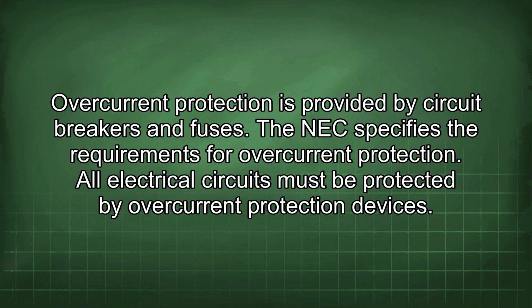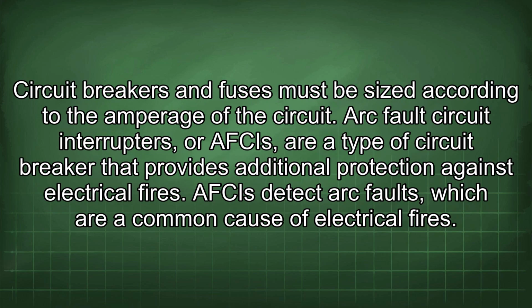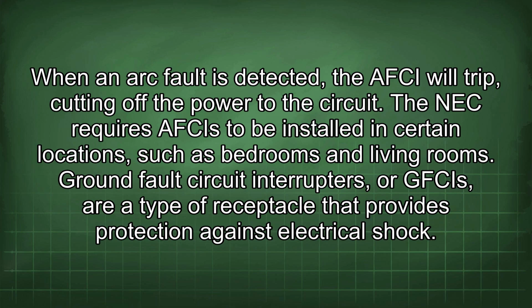All electrical circuits must be protected by overcurrent protection devices. Circuit breakers and fuses must be sized according to the amperage of the circuit. Arc fault circuit interrupters, or AFCIs, are a type of circuit breaker that provides additional protection against electrical fires. An AFCI detects arc faults, which are a common cause of electrical fires. When an arc fault is detected, the AFCI will trip, cutting off the power to the circuit. The NEC requires AFCIs to be installed in certain locations, such as bedrooms and living rooms.